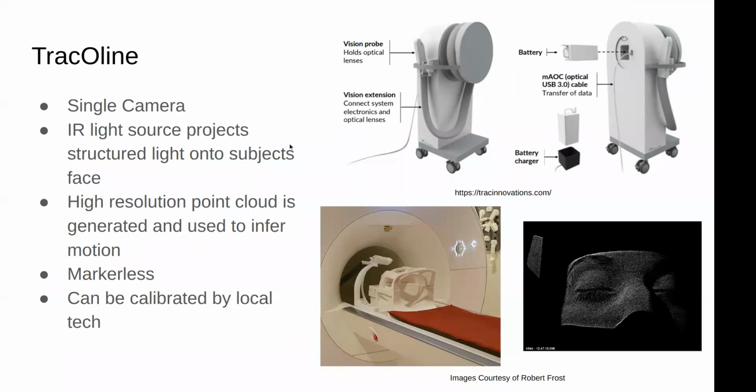Okay, thanks. Can I ask another question? Sure. So generally, I think one of the tricky points with prospective motion correction is that you need to be confident that the measure of motion you've got is an accurate reflection of motion. Otherwise, you'll end up damaging the data more than the actual motion itself. Yeah, and in my experience, that is really tricky. That's why some systems still fall back on the good old bite bars. So what's your experience? Do you have anything like this here?